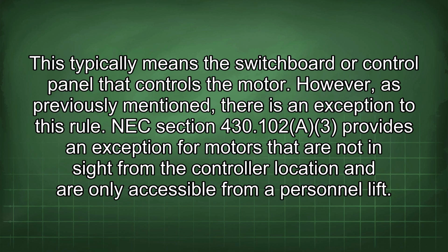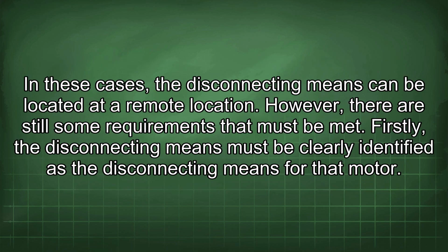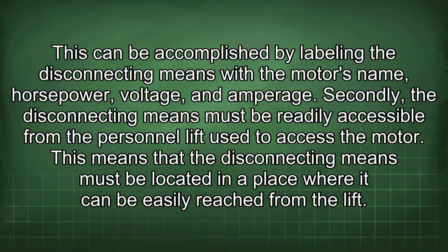NEC Section 430.102(A)(3) provides an exception for motors that are not in sight from the controller location and are only accessible from a personnel lift. In these cases, the disconnecting means can be located at a remote location. However, there are still some requirements that must be met. Firstly, the disconnecting means must be clearly identified as the disconnecting means for that motor. This can be accomplished by labeling the disconnecting means with the motor's name, horsepower, voltage, and amperage. Secondly, the disconnecting means must be readily accessible from the personnel lift used to access the motor.